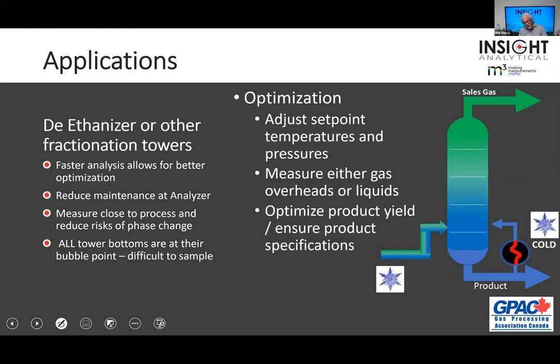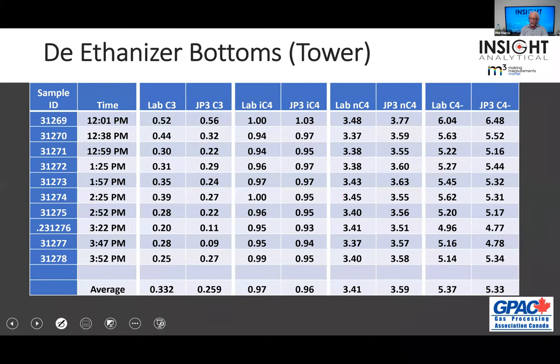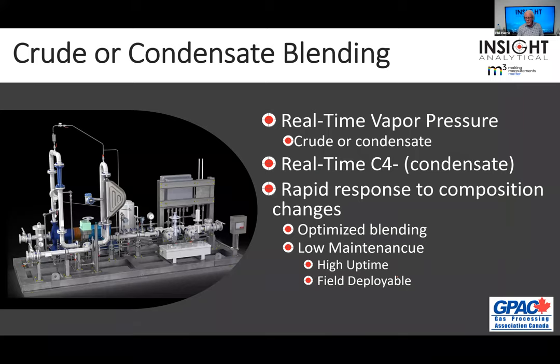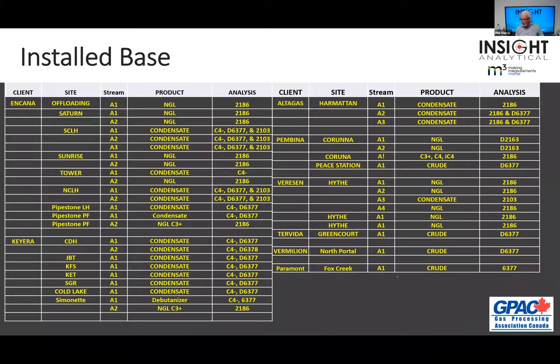The same approach works for de-ethanizers — we want to adjust recirculation rates and hit a C2 to C3 ratio. For de-ethanizers or any frac tower, we control recirc rates and temperatures. Looking at results on the de-ethanizer bottoms: lab result 0.33 versus infrared analyzer 0.26; lab 0.97 versus infrared 0.96 on iC4; nC4 is 3.41 lab to 3.6 infrared. The lab C4 minus and the analyzer C4 minus are almost the same. We can also use this for crude and condensate blending — vapor pressure and condensate quality. Due to time I'll move quickly, but happy to go back on any questions.